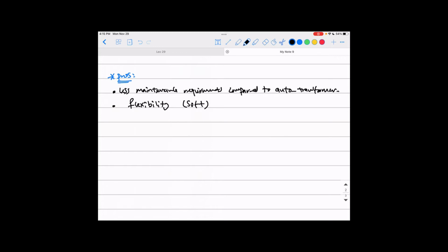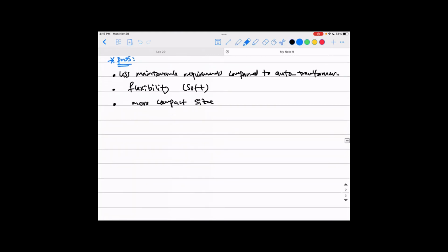But using this, you can have much more flexibility for choosing how much reduction in the voltage you want, and also what is your rate of increasing the voltage back from this reduced value to the rated value after the starting period passes. Okay, guys. And the other thing is the more compact size. If you see a real soft starter, it's not that big. It's a small box you can use just for controlling the motor, compared to having a big resistance to add to the stator or the rotor, or having an auto transformer, which is a totally separate machine. So if size is your concern, that's a good method to go with.